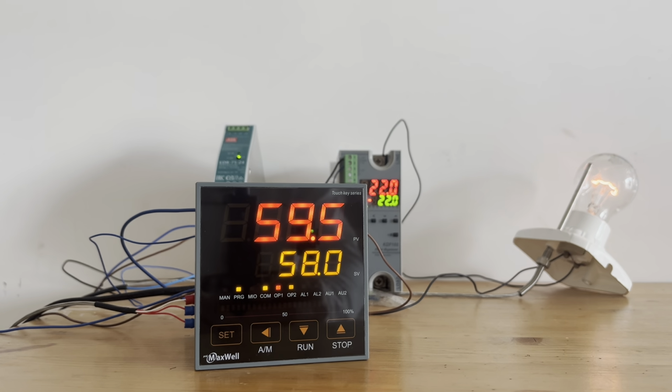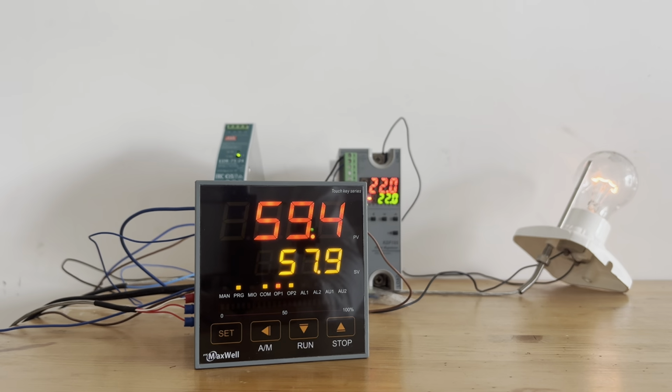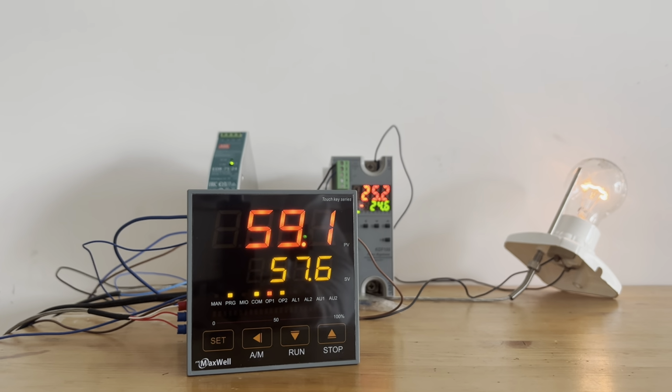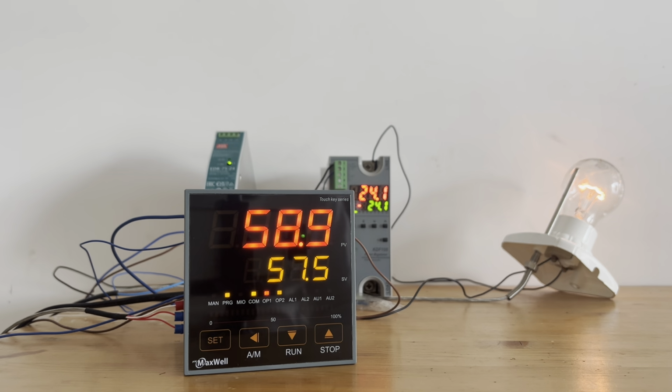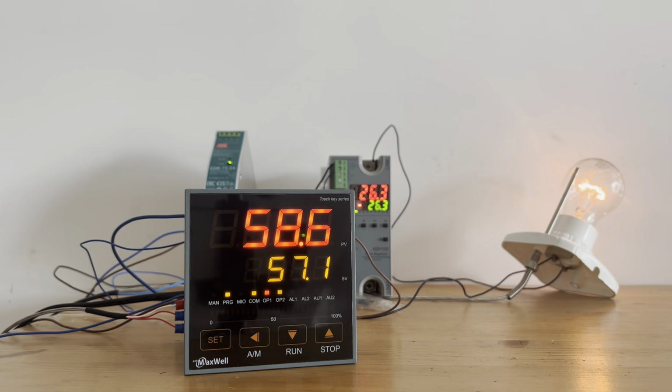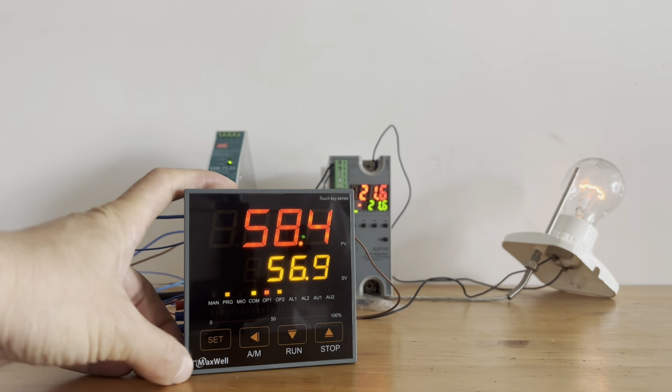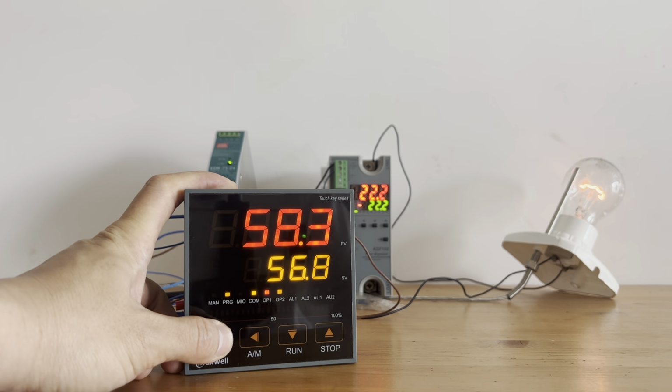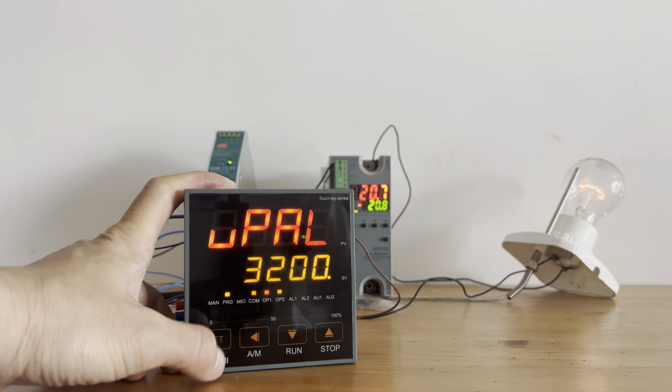Now what if you have a different sensor in your system, let's say type K? You need to change the input, otherwise the temperature reading will not be correct.